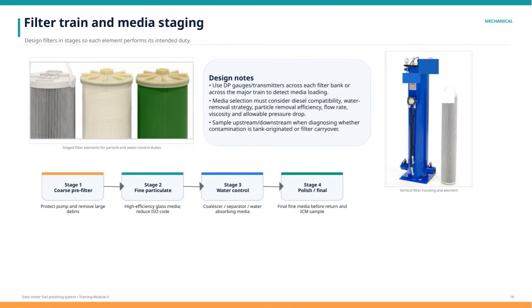Here we have an overview of the filter train and media staging process. The key concept here is designing the filters in multiple stages, with each element fulfilling a specific role to ensure optimal performance. Starting with the mechanical stage, the filter elements are arranged vertically within the housing. Stage 1 uses a coarse pre-filter, which is essential for protecting the pump and removing larger debris from the fuel. This initial step helps prevent damage and ensures smoother operation downstream.